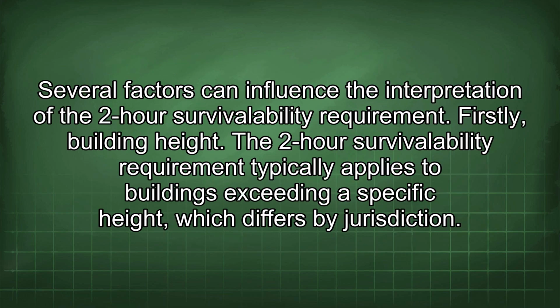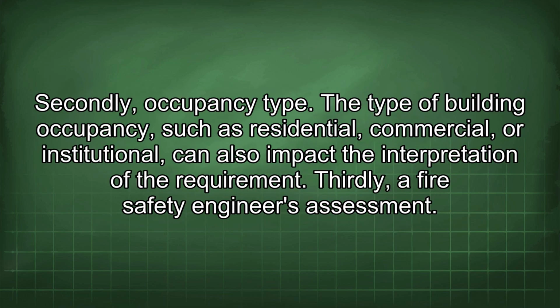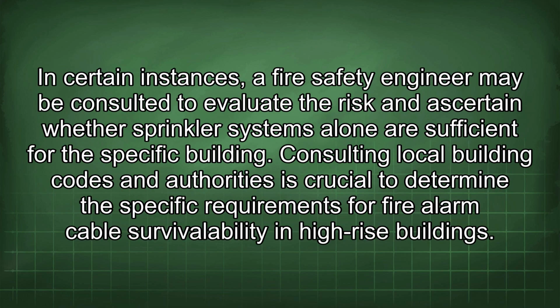Several factors can influence the interpretation of the 2-hour survivability requirement. Firstly, building height. The 2-hour survivability requirement typically applies to buildings exceeding a specific height, which differs by jurisdiction. Secondly, occupancy type. The type of building occupancy, such as residential, commercial, or institutional, can also impact the interpretation of the requirement. Thirdly, a fire safety engineer's assessment. In certain instances, a fire safety engineer may be consulted to evaluate the risk and ascertain whether sprinkler systems alone are sufficient for the specific building.